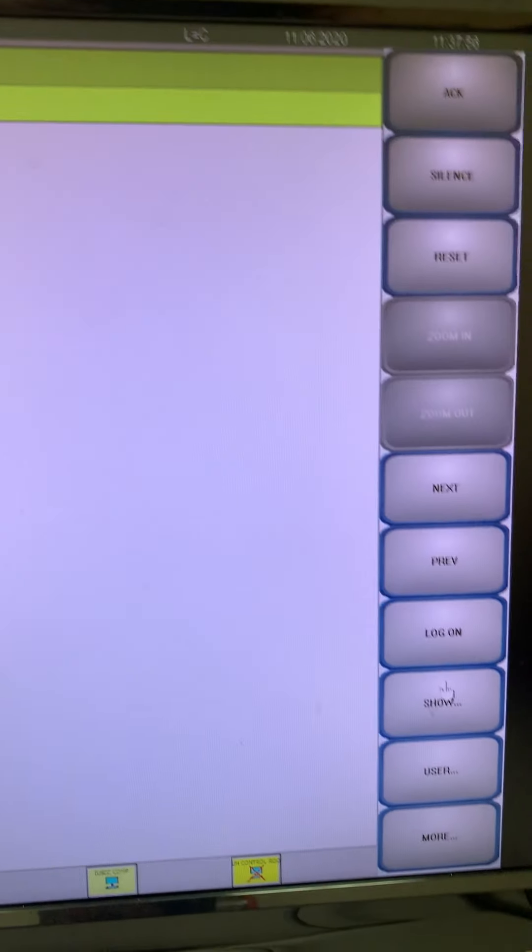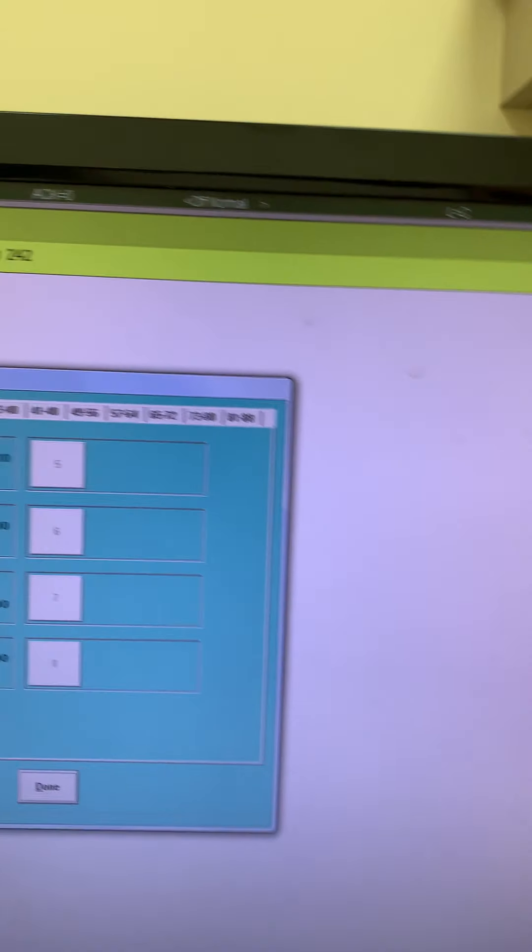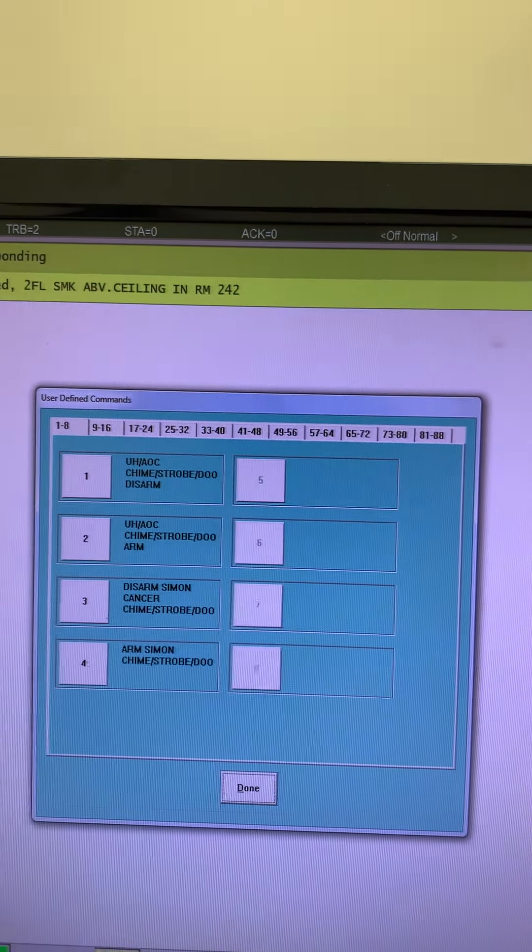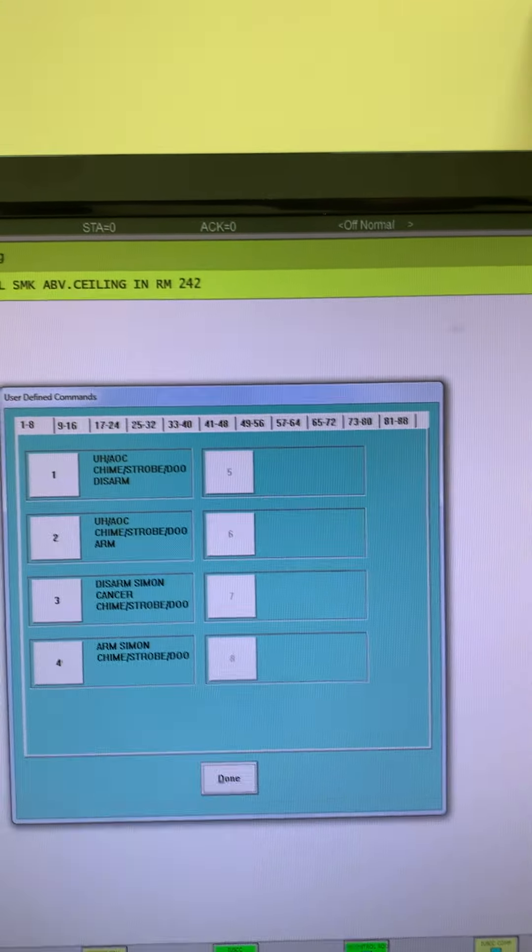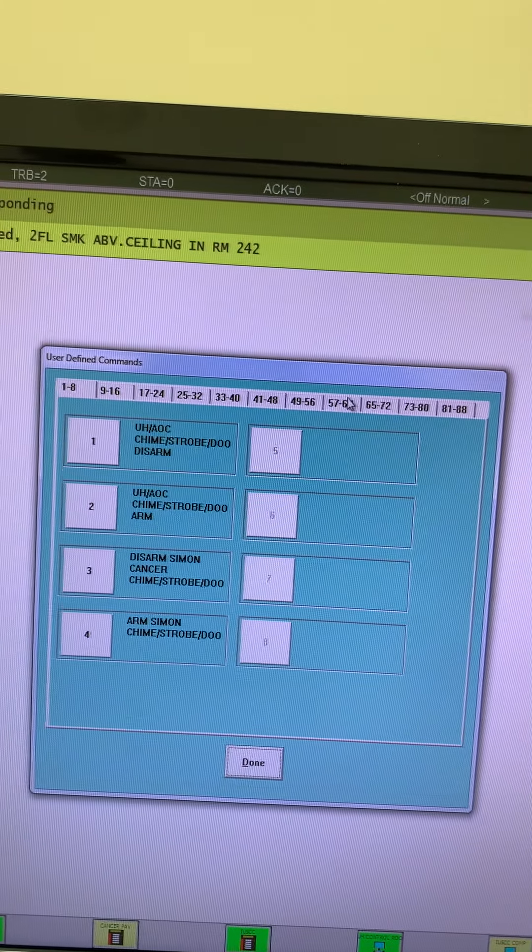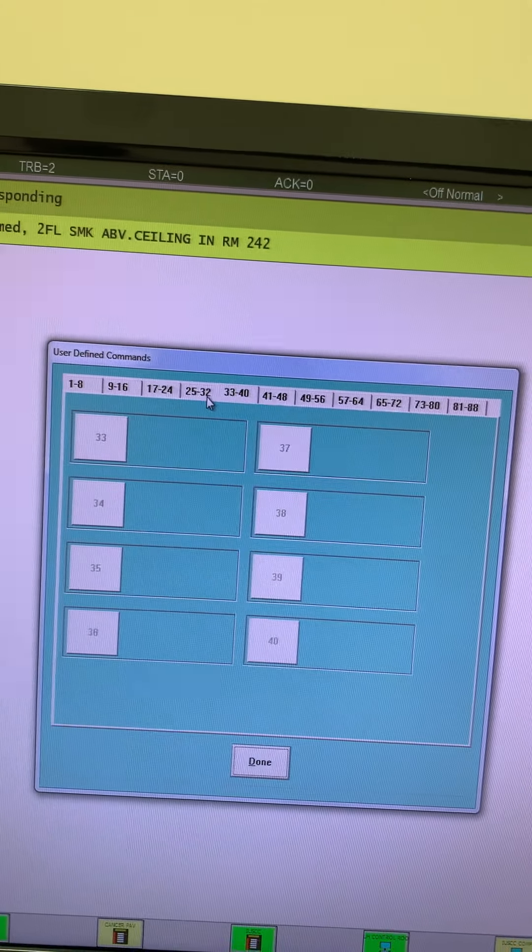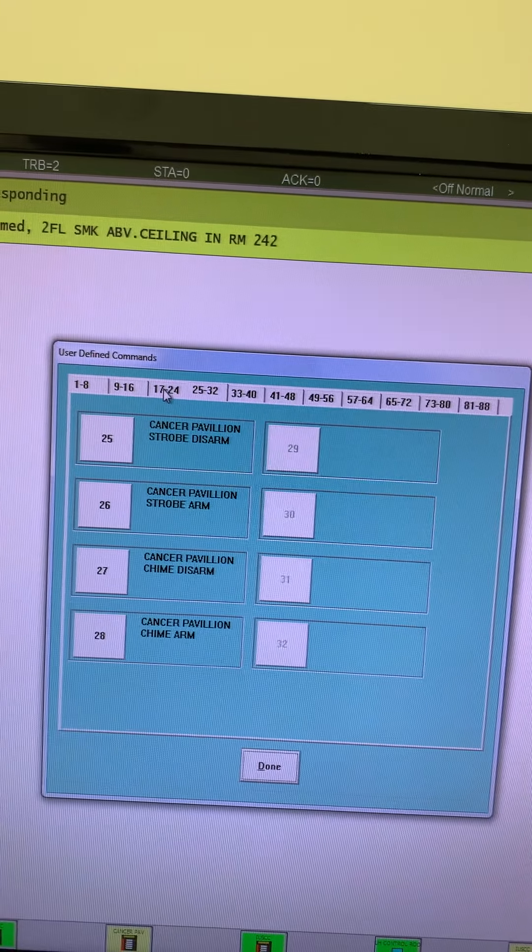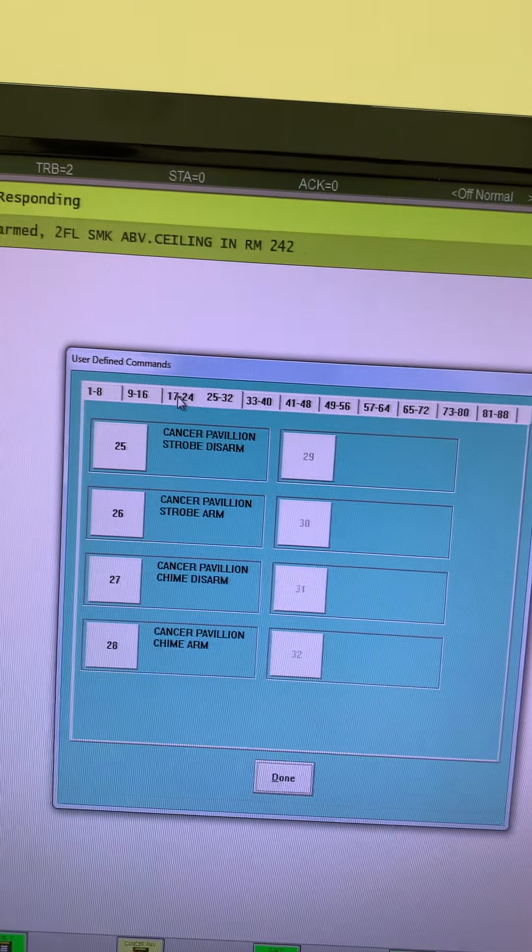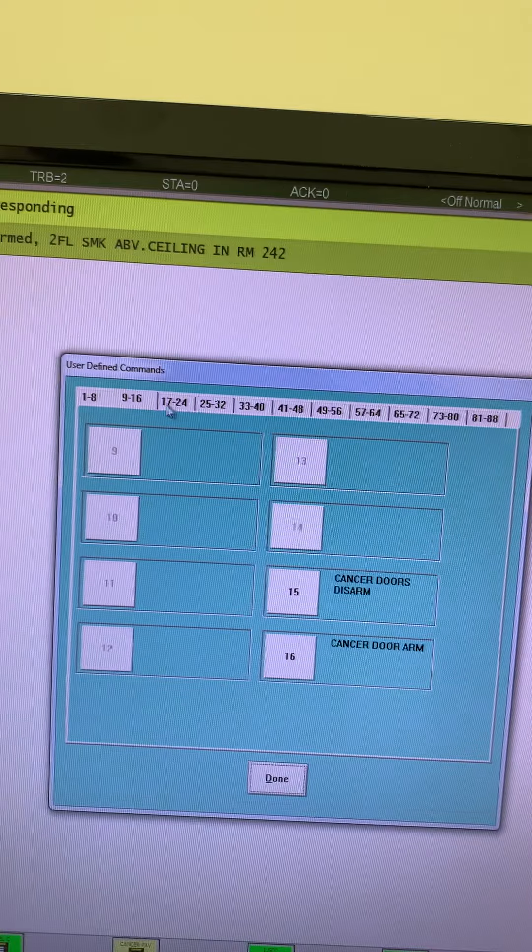Log on is what we use when we want to get real technical and start looking at things. It really enables a lot of these features and these next menus. If I click on the user feature, this is where my bypass options appear. I can bypass horn strobes, doors. We have several different menus on here. These aren't all programmed, but I can do different things in different buildings: disarm strobes, disarm strobes and chime strobes, I can do the doors. There are a multitude of different things we use very frequently when we are testing.